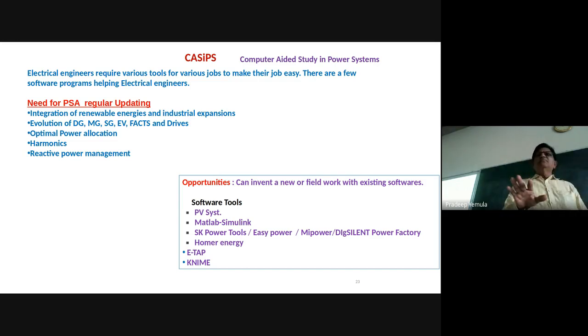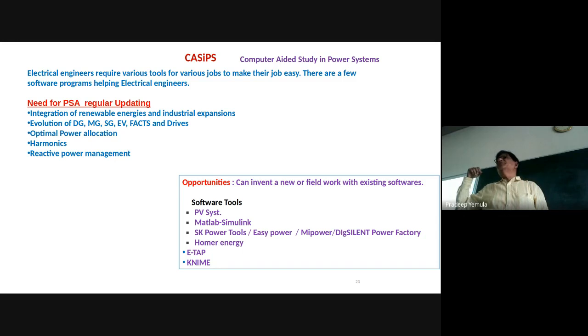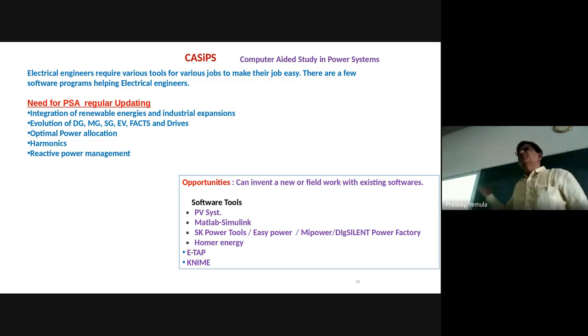If you don't know anything, say for industry, somebody wants to construct an industry, just draw the single line diagram, specify the pumps or compressors, put the load requirement, and leave it to ETAP. It will tell you the size of cable and transformer required. Once done, you ask if any electronic devices are there, what the harmonic levels are, it will tell you where a filter is required. If it's a distributed generation setup, it will tell you where to keep DGs in the diagram. And wherever reactive power is needed, solar power has one more problem: inverters manufactured prior to 2018 don't have reactive power support, so renewable solar will give only active power. Again you have to depend on somebody for reactive power. That is a big challenge, reactive power.